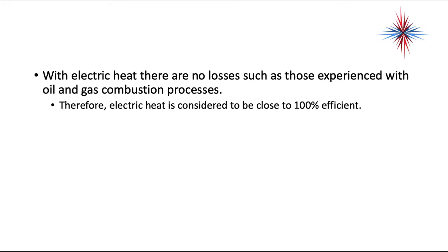With electric heat, there are no losses such as those experienced with the oil and gas combustion process. Therefore, electric heat is considered to be as close to 100% efficient as we can get. Remember, with gas and oil, we lose part of our heat out of the combustion process. It goes out the vent. Even with 90% efficient furnaces, we lose heat. When we don't have to vent the air, we get 100% of the heat generated into the space.